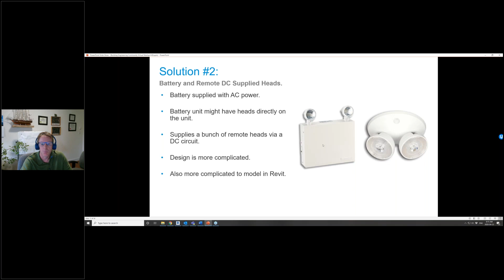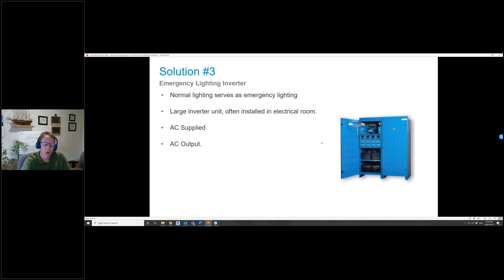Next solution is an emergency lighting inverter, usually more appropriate for a larger building. This is an inverter unit, and this is a big one I show here, usually installed in the electrical room. So AC power comes in, comes through this unit and goes out to the lighting systems. And if power goes out, this will take over. It's a giant UPS and it will supply AC power when the building is out of utility. So the normal lighting circuits and lights serve as your emergency lights.